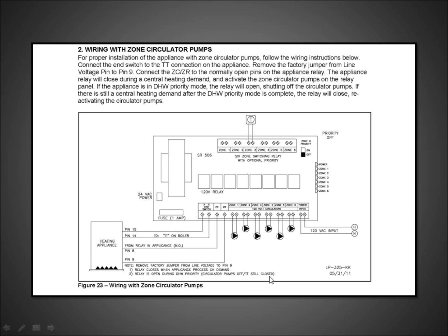Since we don't need an individual pump off of our unit to circulate the water because there's no pressure drop through our system. The note 2 says the relay is open during a DHW priority, circulator pumps off, TT still closed. So what we're doing is we're shutting these pumps off. We're now giving priority to the pump circuit that's internally wired within the Versa Flame, and we're providing DHW priority. The functionality of that works the same with any of our low-mass boilers.